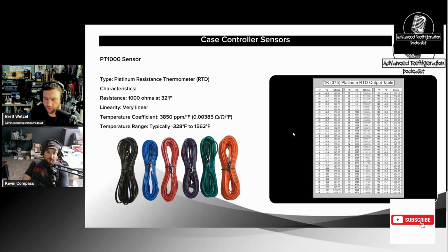You can see right here, if you go from 940 ohms to 944, just 4 ohms, you're basically increasing that by 2 degrees, right? That's why on case controllers with Danfoss you never have to do offsets. It's so damn close, and generally the sensor wire is landed right on the board.